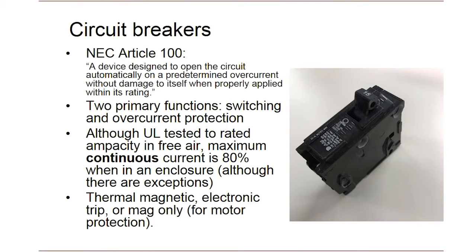Now let's talk about circuit breakers. The NEC definition is: a device designed to open the circuit automatically on a predetermined overcurrent without damage to itself when properly applied within its rating. Basically, a circuit breaker can be opened and closed against all magnitudes of current up to its short circuit current rating. The UL standard that normally applies to most circuit breakers is UL 489. These breakers use either a thermomagnetic trip element or a solid-state electronic trip element.